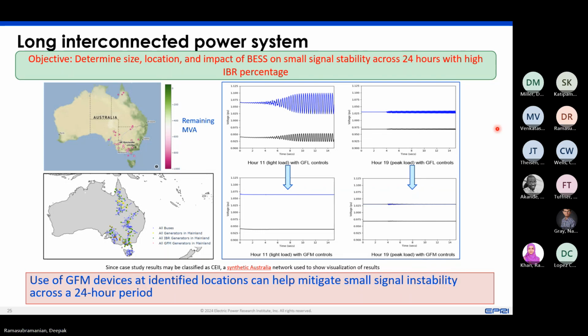And last question. You said for the fast response, the response time was less than 1 second. Does that consider all the communication delays between plant and inverter level control? Okay, so that's the nuance there. Because it's put down to the inverter level, there isn't any communication delay, because you are responding at the inverter level. So whatever delivery of response that you're seeing at the plant level is the delivery of response that you're seeing at each of those individual inverters. So the communication delay that exists between the plant and the inverter is taken out of the picture.